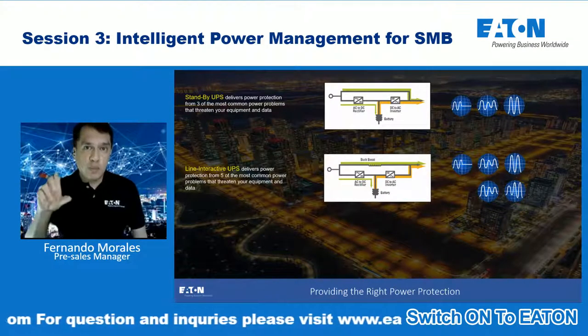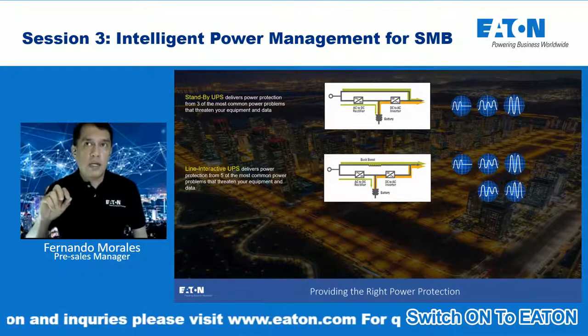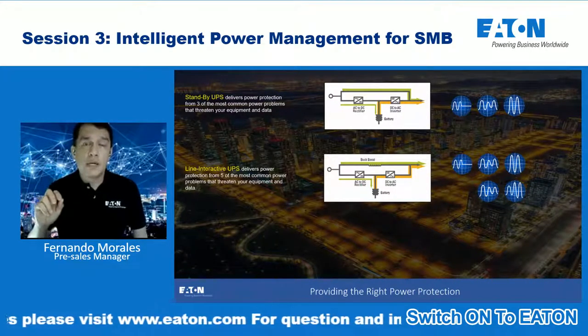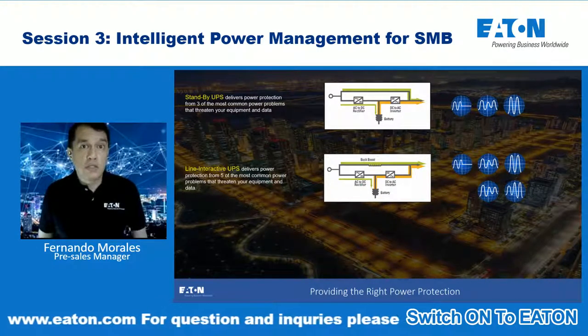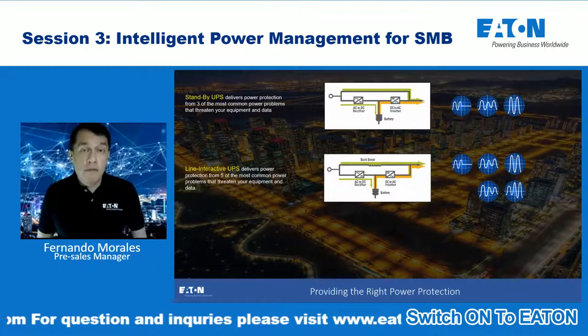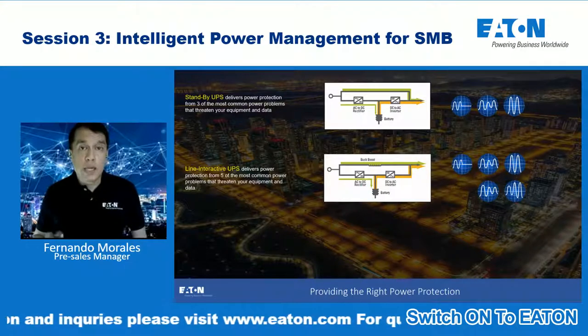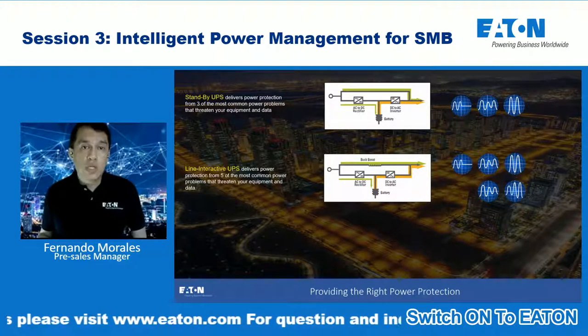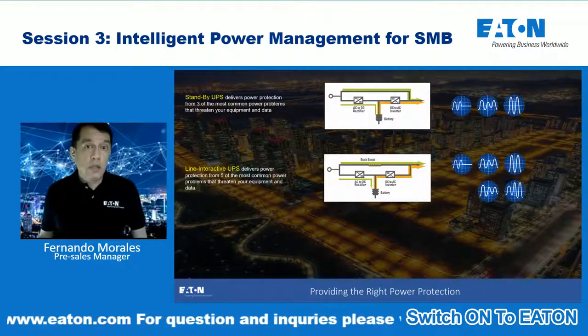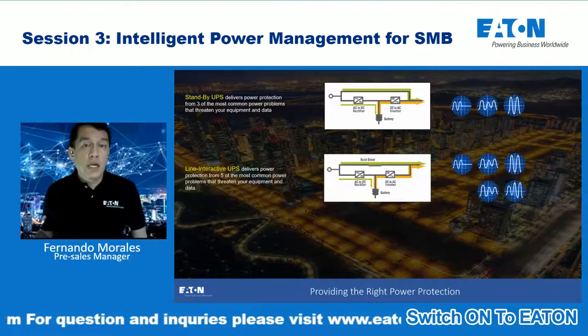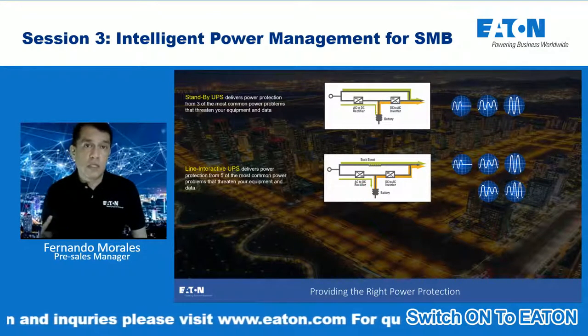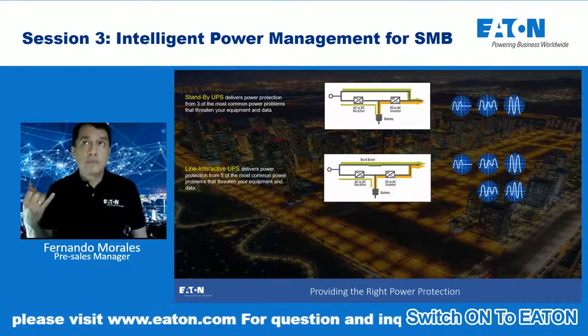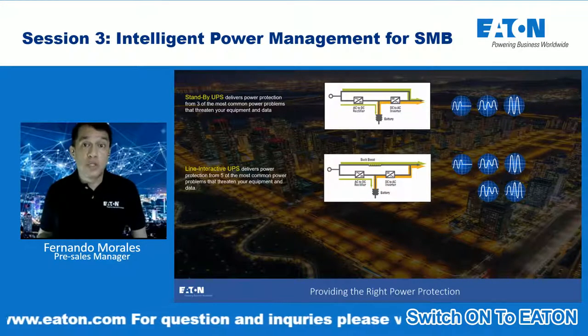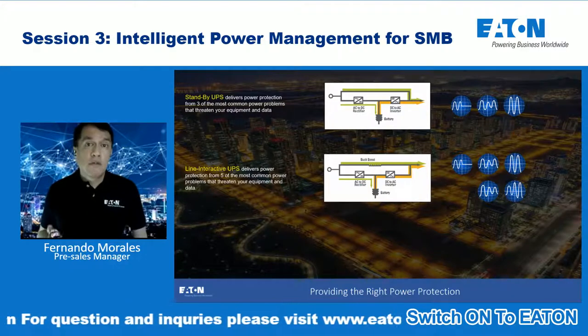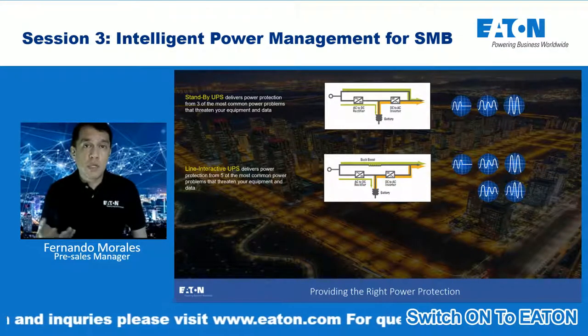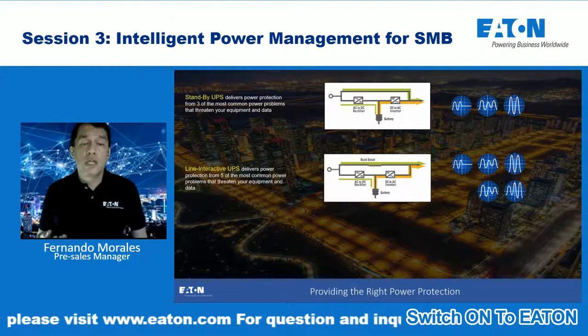So the UPS still needs to detect a surge in power or hit a predefined voltage limit before the AVR will function. So the AVR is not really true online working, but there's still an AVR to correct any high voltage or low voltage condition, which a standby UPS cannot. That's why for a standby UPS, it can correct typically three power disturbances: power failure, voltage sag, and voltage surge. For the line interactive, it can correct five power disturbances: power outage, sag, surge, high voltage, and low voltage.